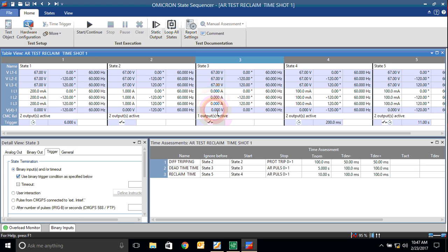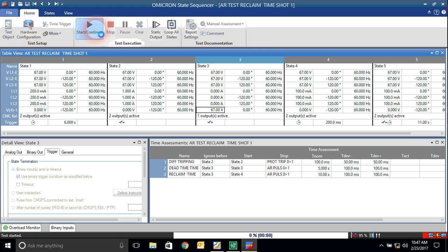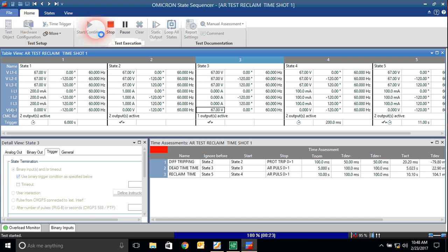Now as I perform, I will take phase and the ground. Here, done. Now I satisfy the sync. So as you will see, this function will bypass with no problem, the closing sequence will be okay, and the short time will be okay, everything will be nice, because the sync function is embedded and the sync condition is satisfied, so the relay works without any problem.